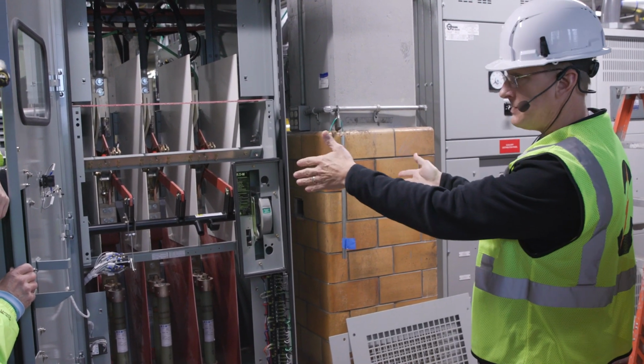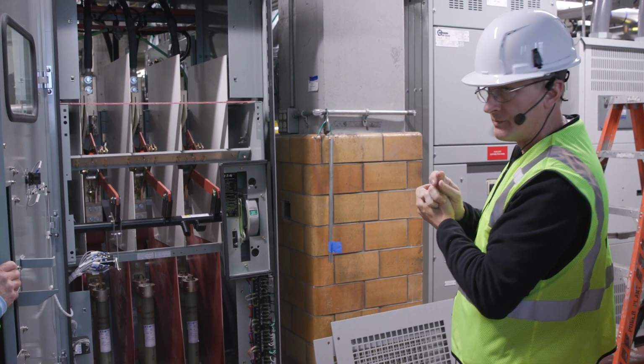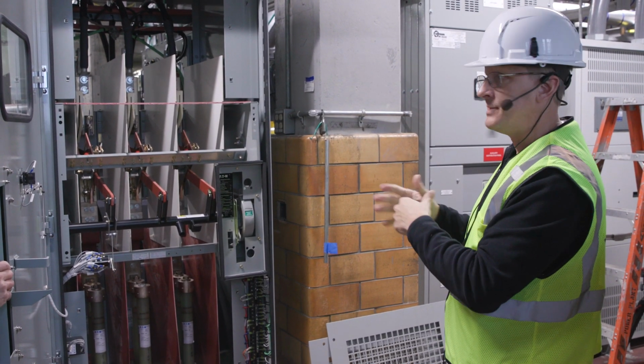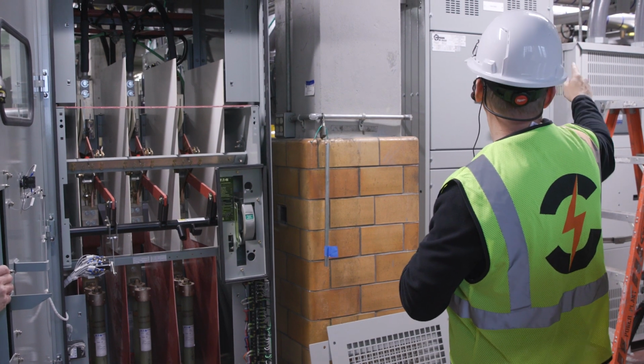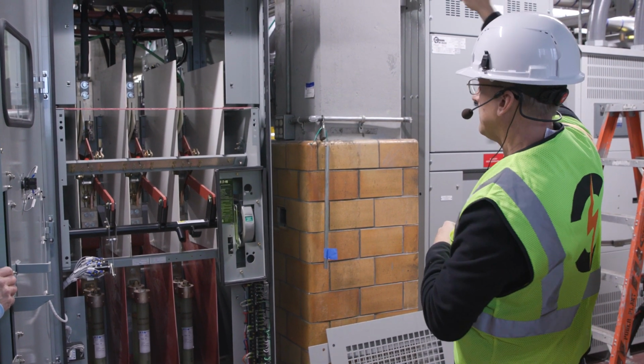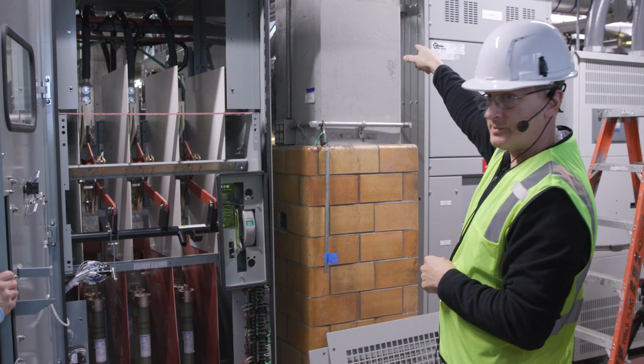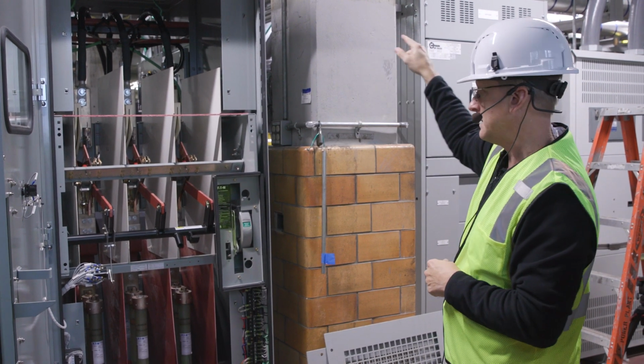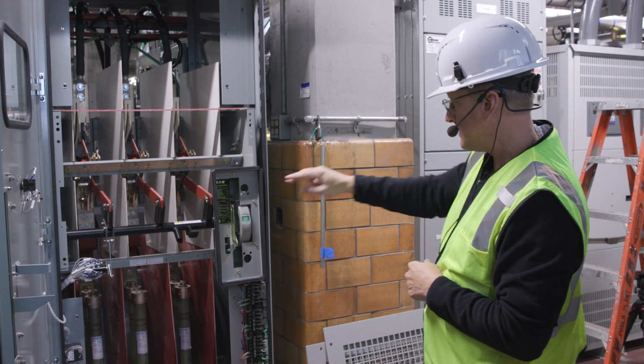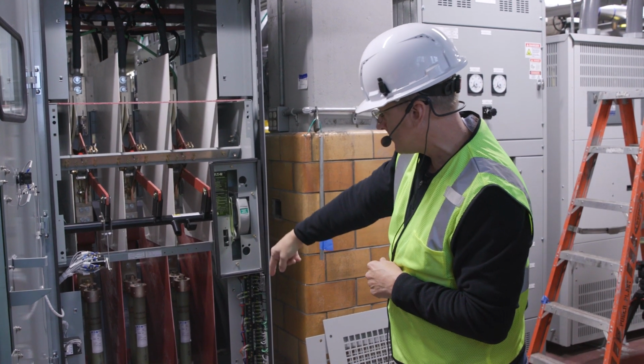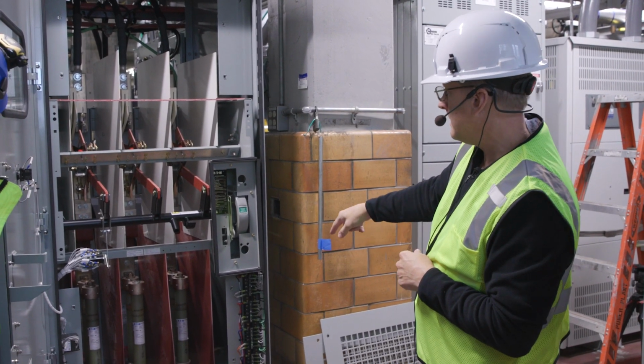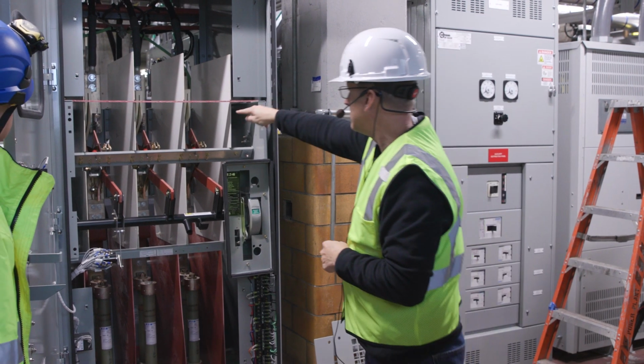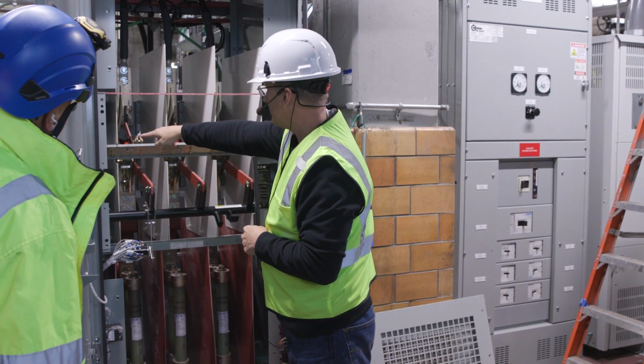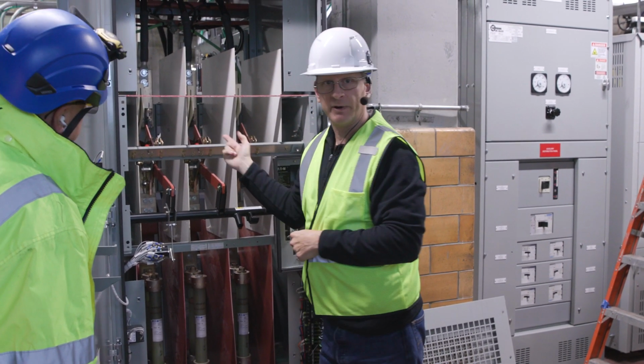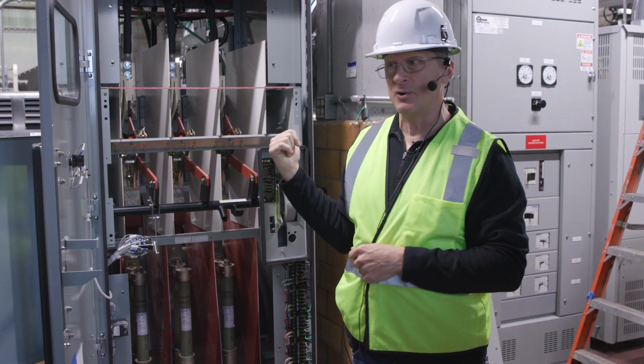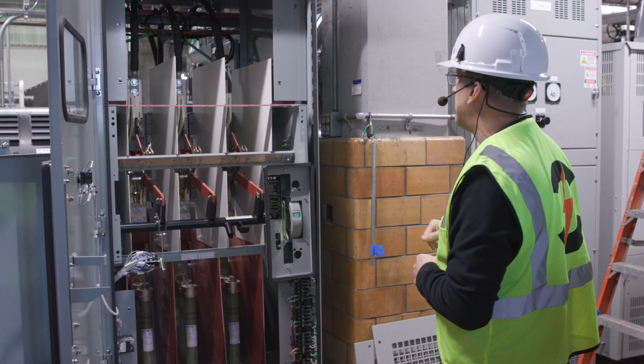And then right here, you see that's already open. This is our generator disconnect. Also medium voltage. Comes from the choke, the tap of the choke, through the GDP, into the generator, all medium voltage. Again, it's a disconnect with a fuse as well, so it's a fuse disconnect. And here you can see the grounding blades that effectively ground it from the generator side when the disconnect is open. So those will be taken out. Okay.